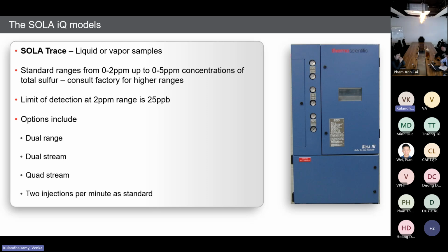Also, the limit of detection range is 2 ppm to 25 ppb. It is able to detect down to 25 ppb, parts per billion. This is the lowest detection range, 25 ppb. So this also has dual range, dual stream, quad stream, and 2 injections per minute as standard. Actually, for low sulfur measurement, we need 2 injections per minute. That means every 30 seconds, one sample injection, which is called semi-continuous injection.